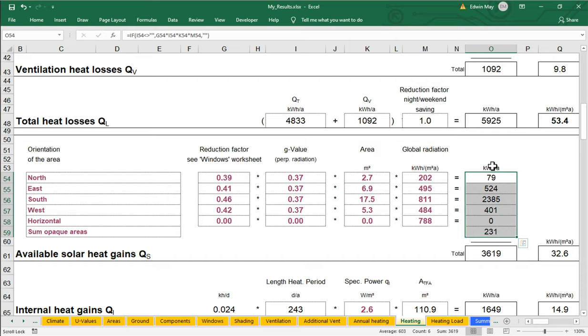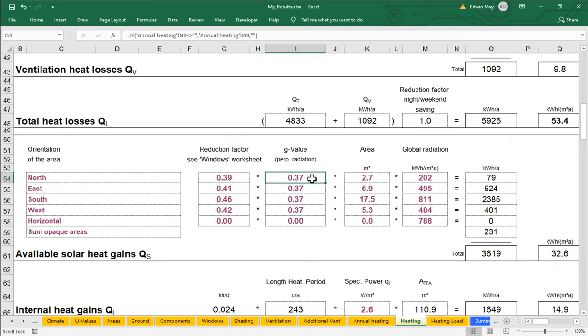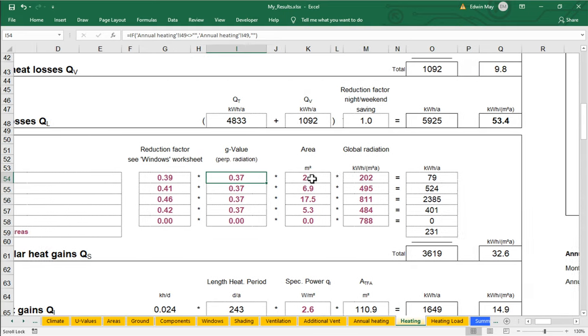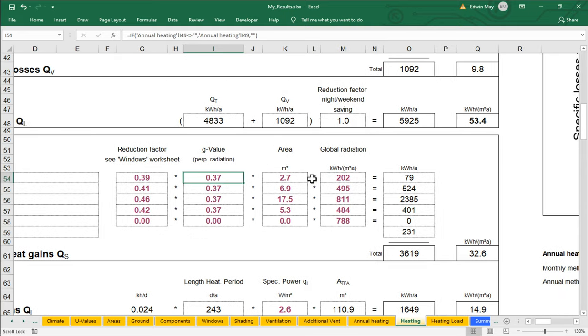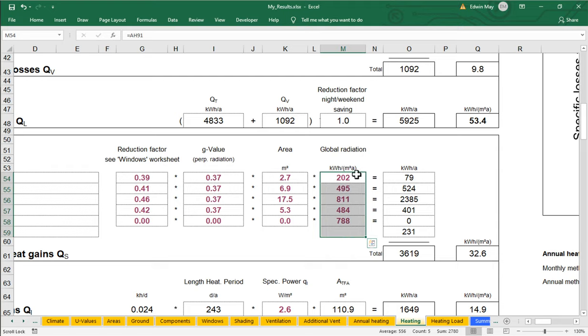We take the so-called reduction factor for the windows for that orientation. We'll come back to that. We multiply it by the G value, the solar heat gain coefficient, roughly. They're not really the same thing, but they're more or less the same thing for our purposes. Times the area, times something called the global radiation. This here, this is just climate data. That's all this is. This is just local climate data. This is going to change if you change your location of your building.